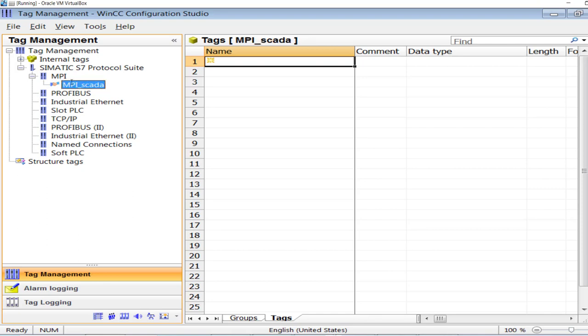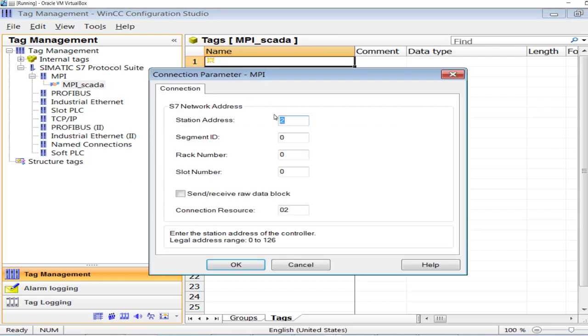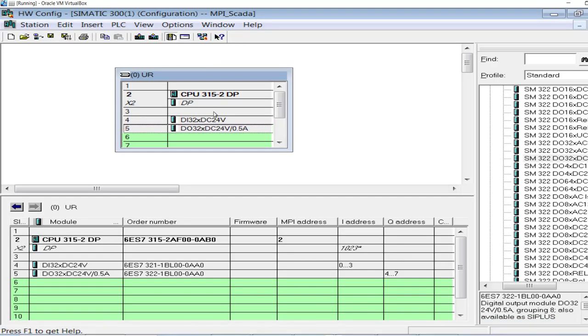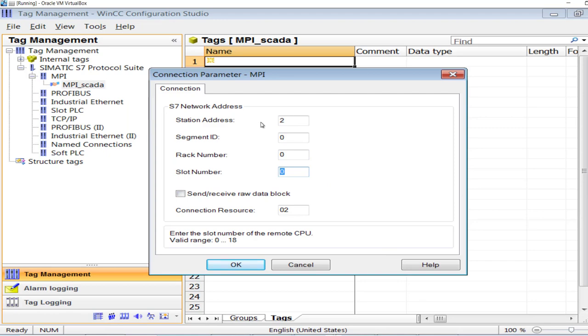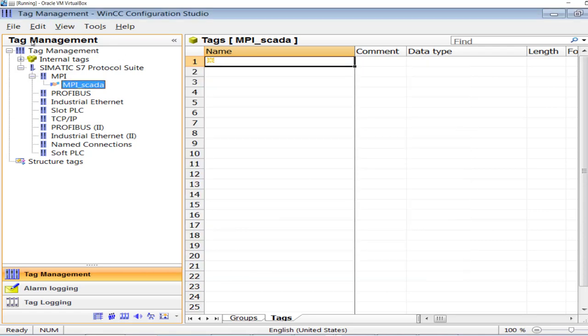Create a new connection and name it 'MPI_SCADA'. In the connection parameters, enter the slot number. If you go to the physical hardware configuration of the PLC, you'll find rack zero, and in slot two we have the S7 300 PLC CPU. The CPU has the MPI port to which we connected the MPI cable. In the WinCC Tag Management connection parameters, enter slot number 2 and rack 0. You are done with the connection between WinCC and the S7 300 PLC.